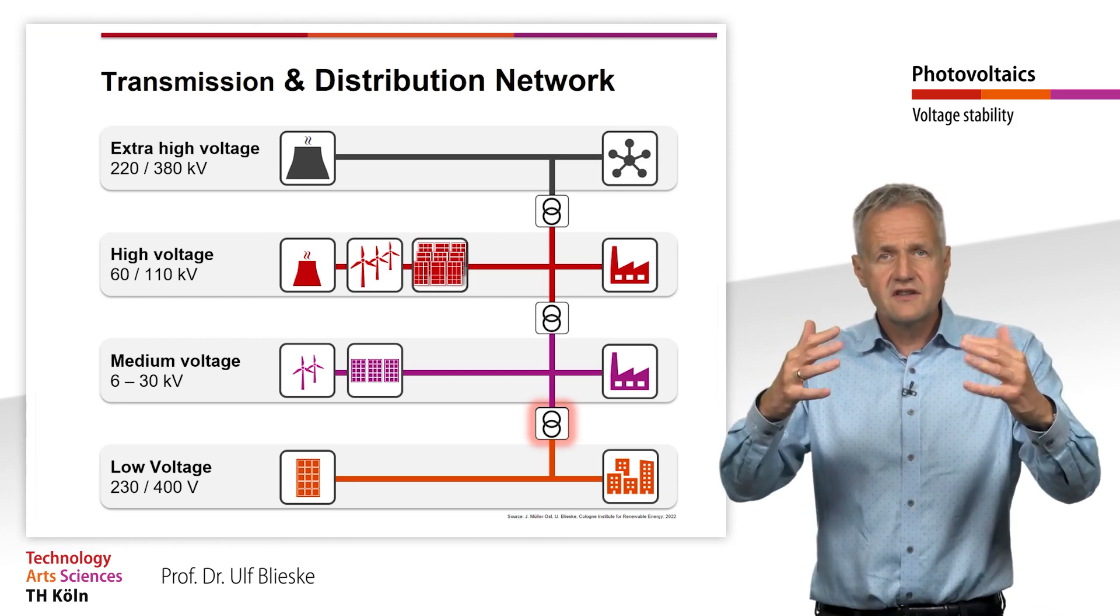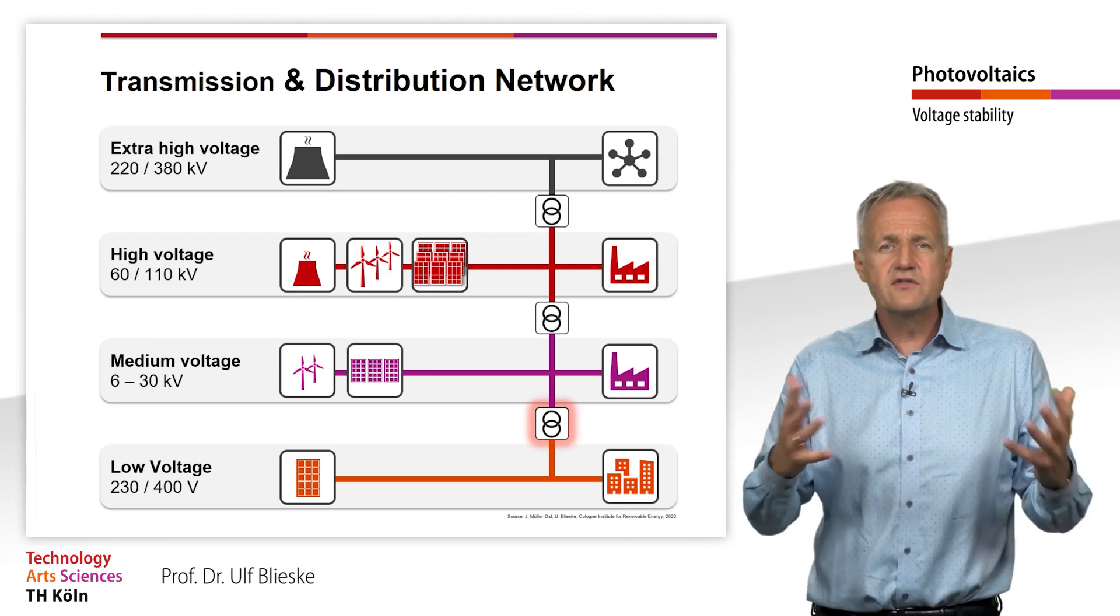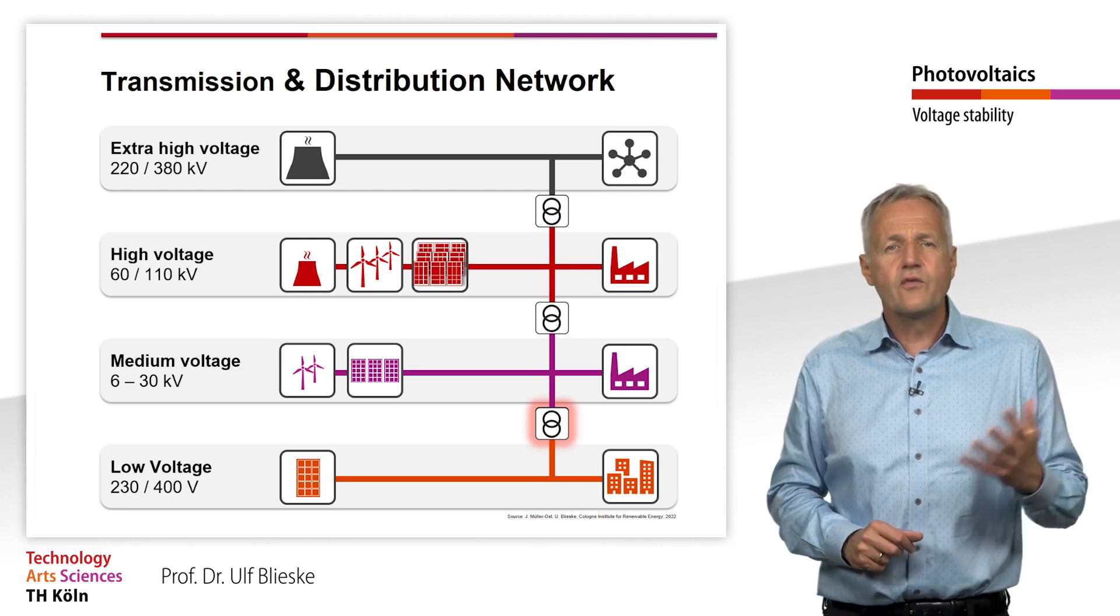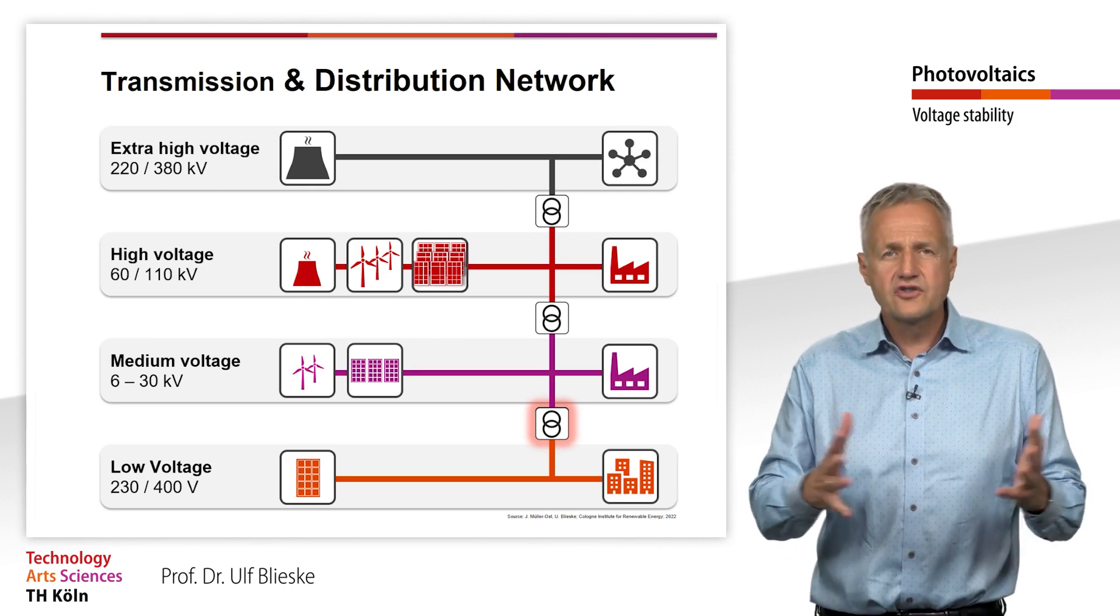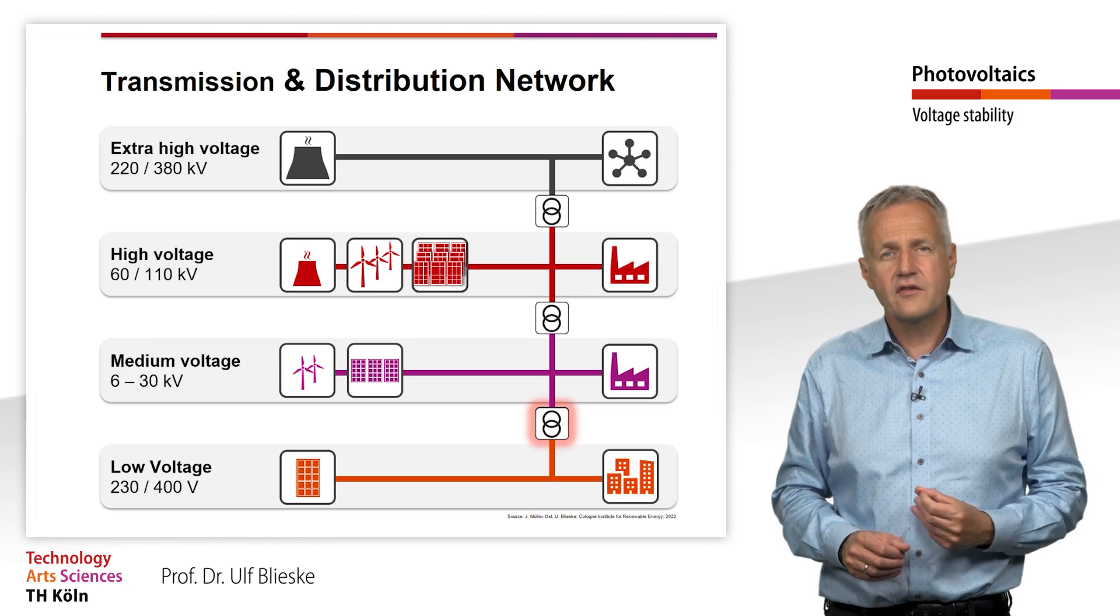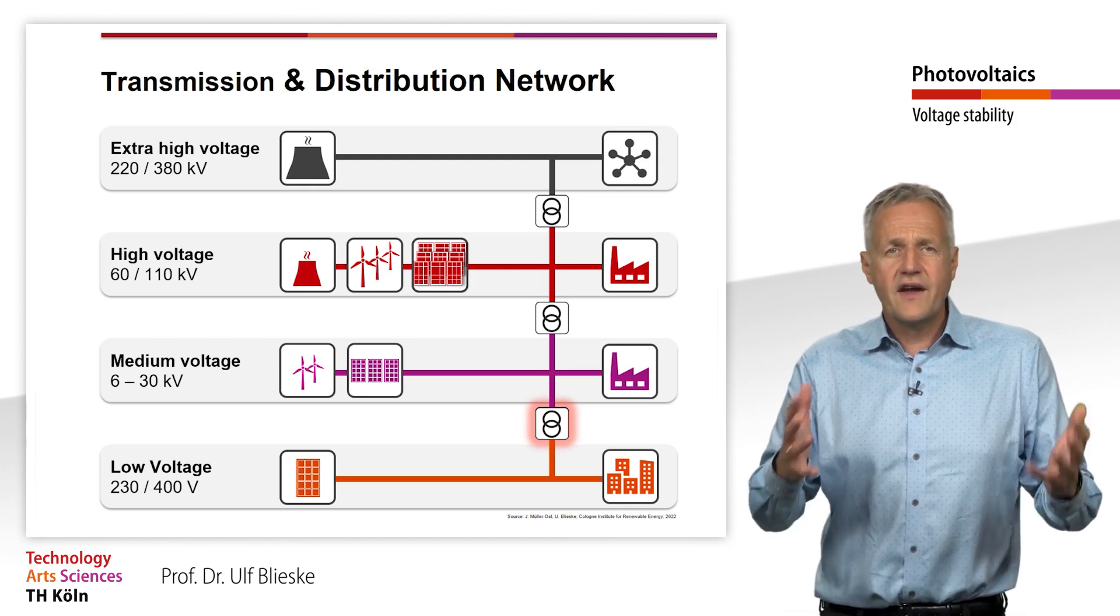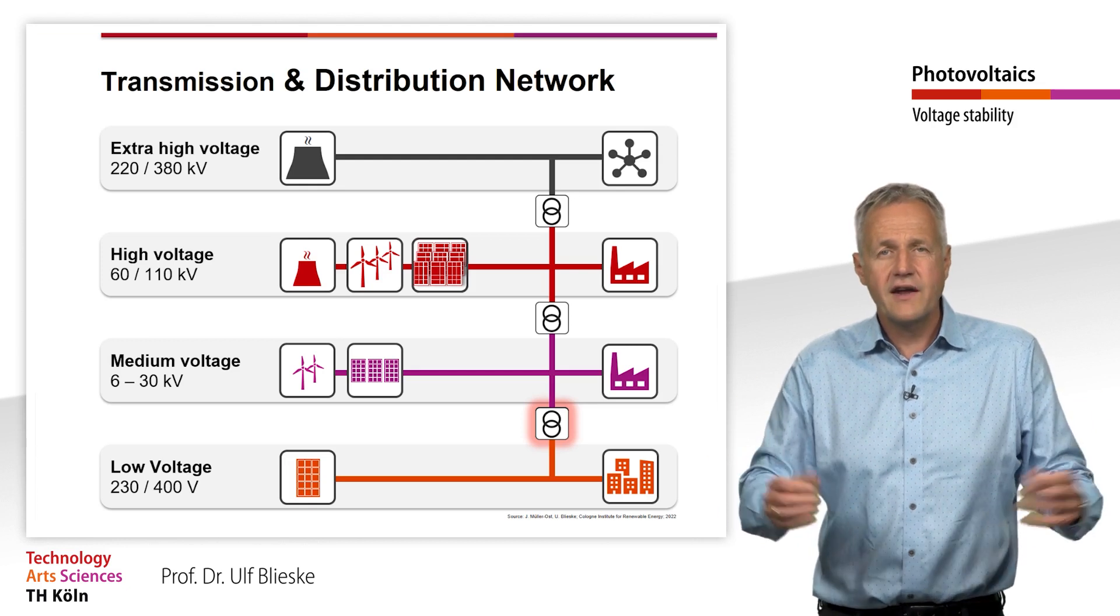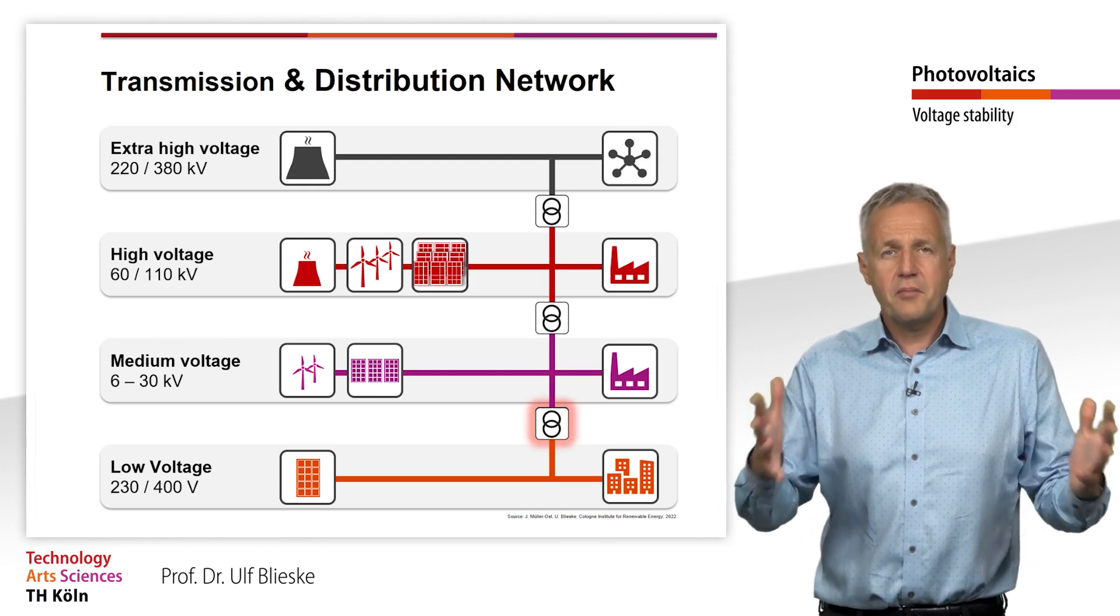Over-voltages stress the insulation and reduce the lifetime of the equipment. Under-voltage, on the other hand, can in the worst case lead to an uncontrollable drop in the mains voltage. This effect is called voltage collapse and can lead to a complete or partial failure of the power supply system.